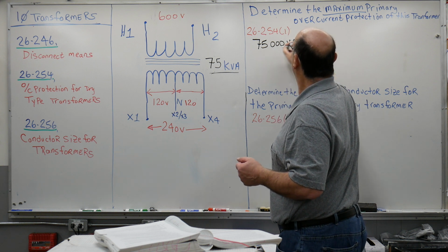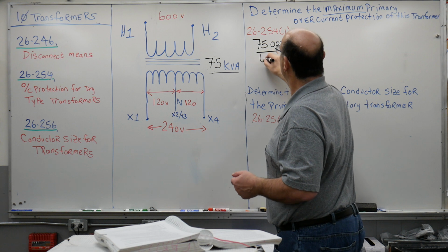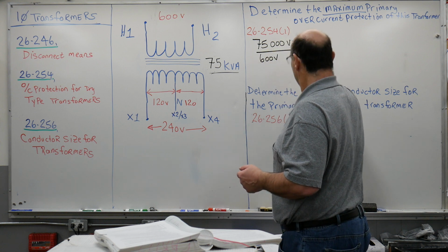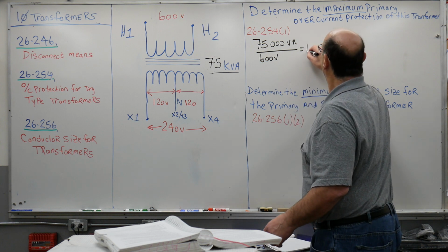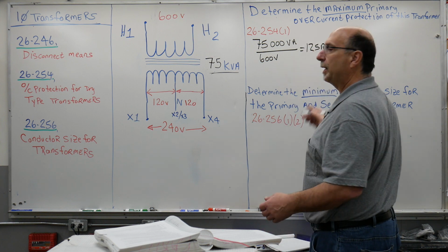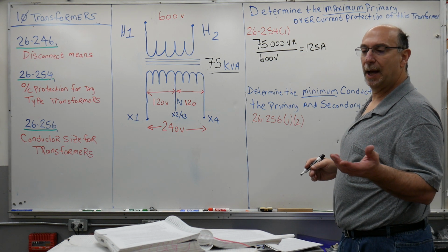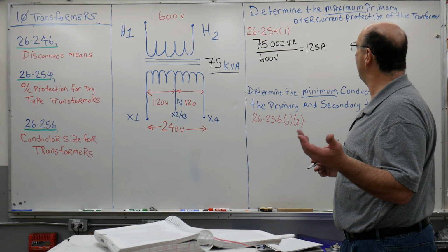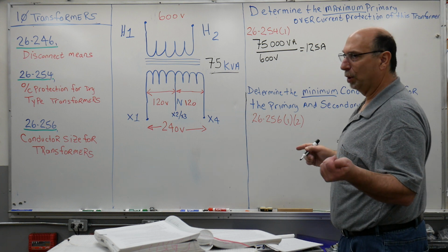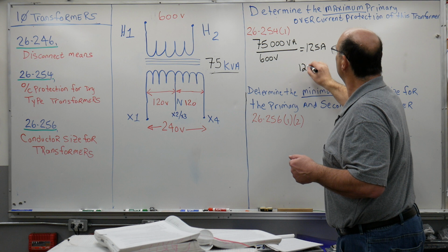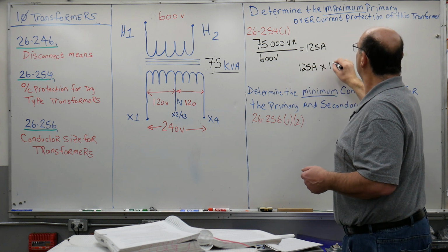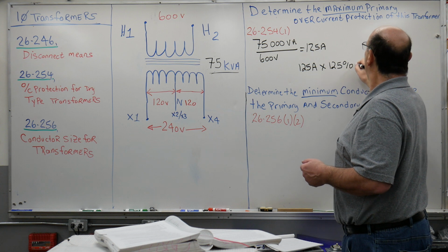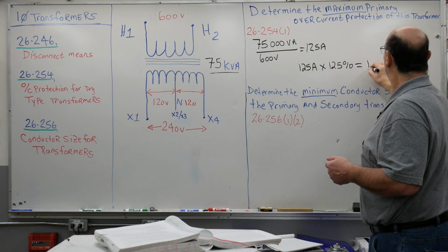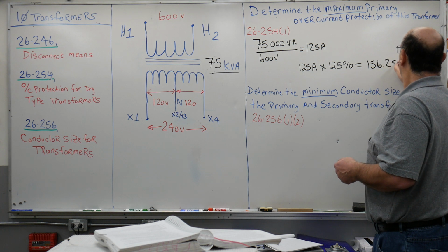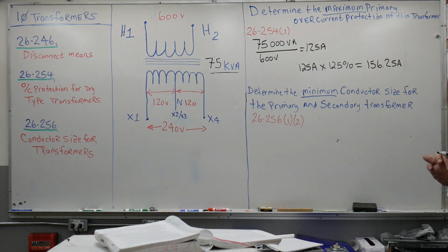75,000 VA divided by 600 volts. We have a current of how much? 125 amps. We then, of course, have to throw in the 25% safety factor here in accordance with Subrule 1. We then take 125 amps times 125%. And lo and behold, we come up with 156.25 amps.